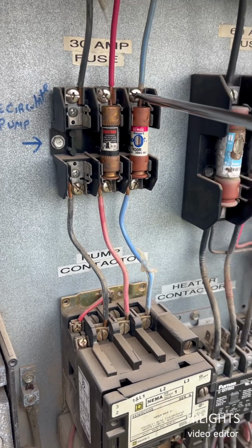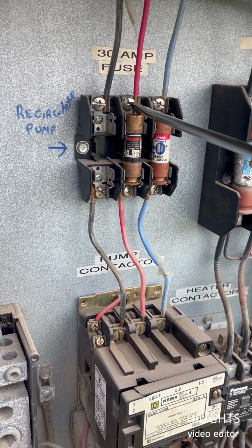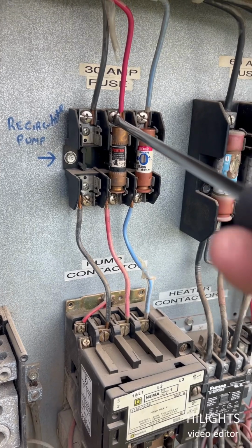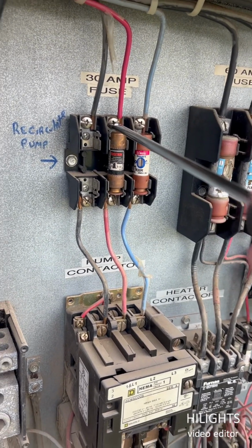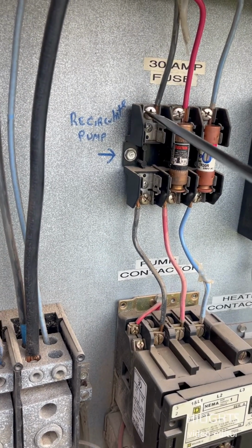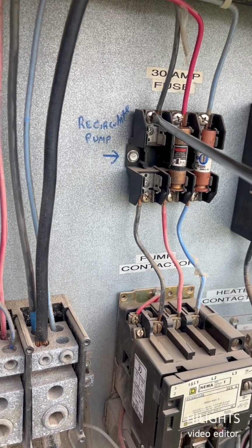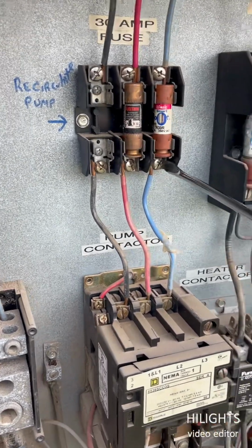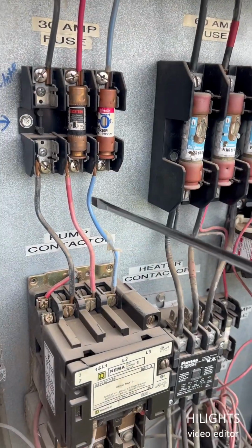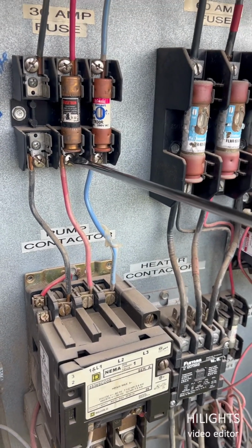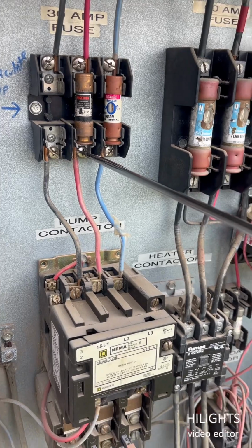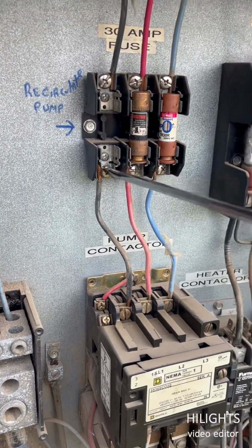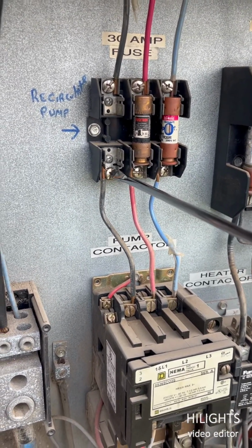Also, what you want to check are these screws up here, because if they're loose like these, look at that. That could definitely pop a fuse, trip a breaker, arc. So yeah, want to go ahead and tie those down. I found 4 of them that were really loose. So make sure those are all tied down, because that could cause the fuse to pop also.